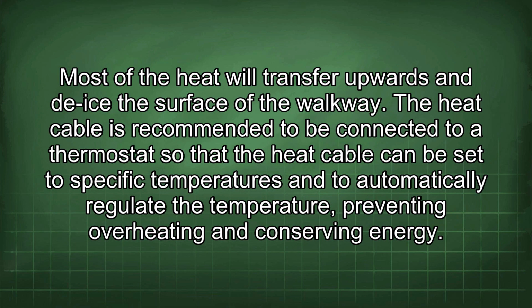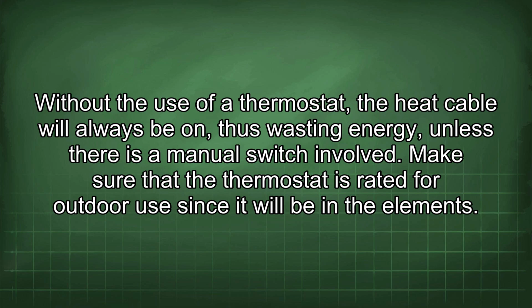The heat cable is recommended to be connected to a thermostat so that the heat cable can be set to specific temperatures and to automatically regulate the temperature, preventing overheating and conserving energy. Without the use of a thermostat, the heat cable will always be on, thus wasting energy, unless there is a manual switch involved. Make sure that the thermostat is rated for outdoor use since it will be in the elements.